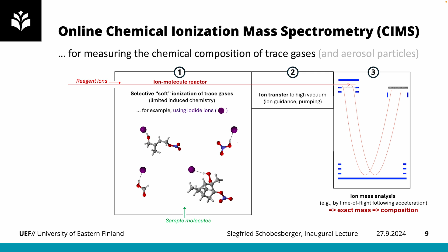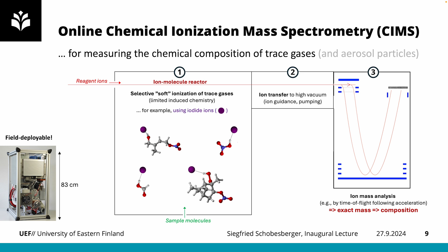Some examples shown here. Now that these molecules are ionized, we can manipulate them with electric fields, and we can transfer them into mass analyzers, which usually requires a high vacuum. An example mass analyzer is shown here, which separates ions based on their time of flight, exploiting the fact that heavier ions will fly more slowly after being accelerated by the same electric field as lighter ions. Then we can measure the exact mass of those ions, and from the exact mass we obtain their composition. Another key feature of the instruments we like to use is that they're fairly compact, and we call that also field deployable, because we can deploy them into the field.